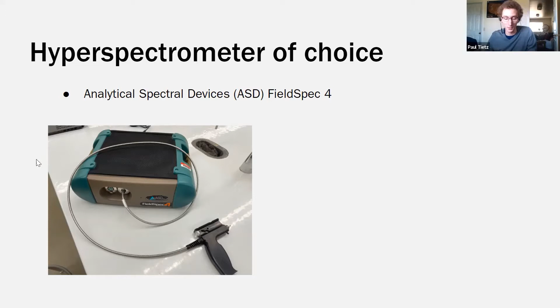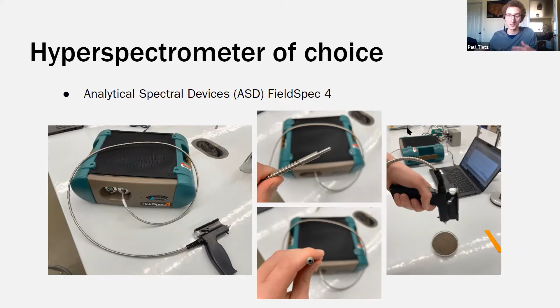The light that enters the probe travels through fiber optic cables within this steel cable here into the instrument where the wavelengths are read, and a readout on the connected laptop shows the spectral reflectance graph and all of the wavelength data. So this little handle here is the palm grip that just makes carrying the probe and aiming it a little easier. You can pack up this whole system into a backpack and carry it into the field. And every time you click the spacebar, the probe will record the reflectance data from 350 to 2500 nanometers of whatever object you're aiming at.